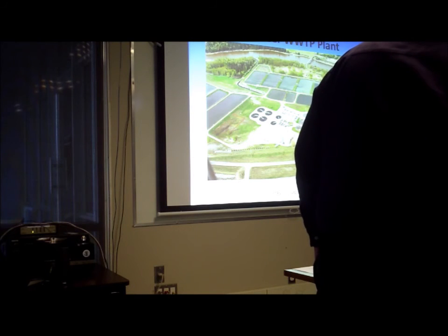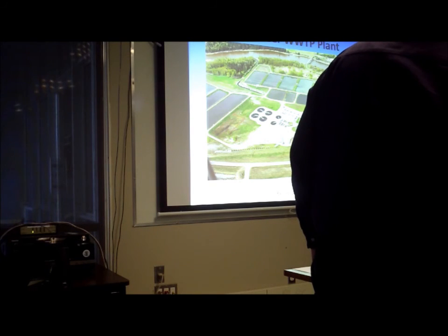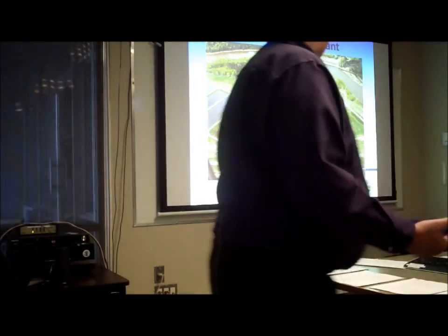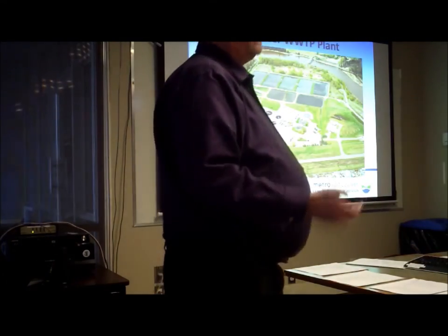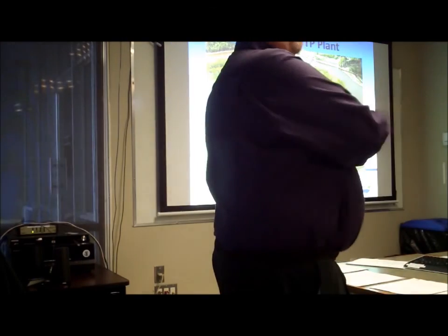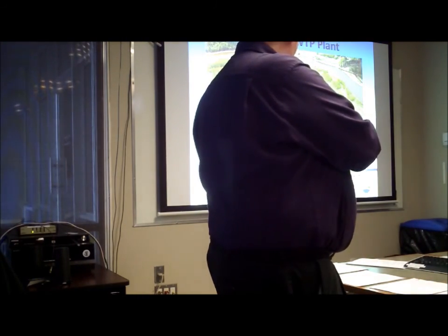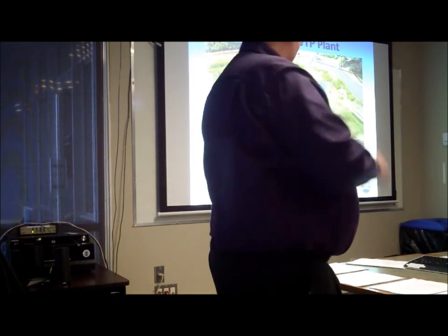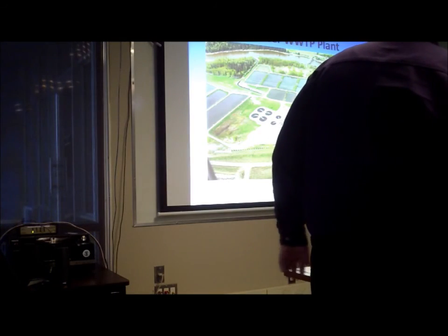So we would pump primary sludge at 1% over the fermenters and try to have a 5-day solids retention time. Like what we battle here at Iona with soluble BOD, we wanted to do that because that enhances the biological phosphorus removal in a BNR plant.